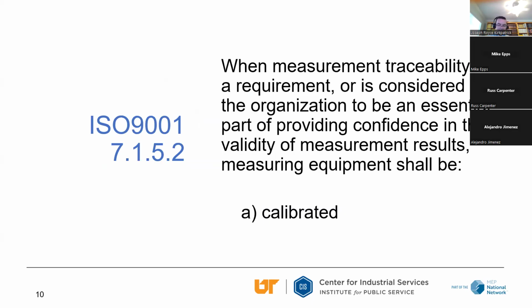And you'd have a hard time convincing me that any gauge you have on the floor that we're using to check parts, if it's marked reference only, why is it there? Do you not need to have confidence in that measurement? And honestly, I would recommend that if you have reference only gauges, you really need to think about what you are using that gauge for, and do you need to have confidence in that measurement? And if you need to have confidence in the measurement, sure, that needs to be calibrated.